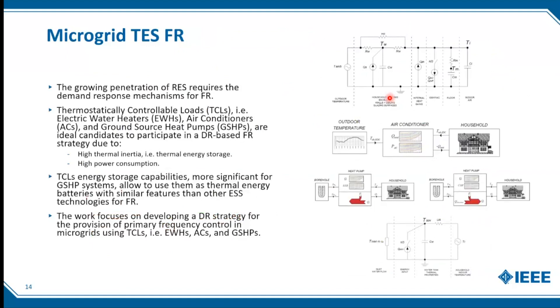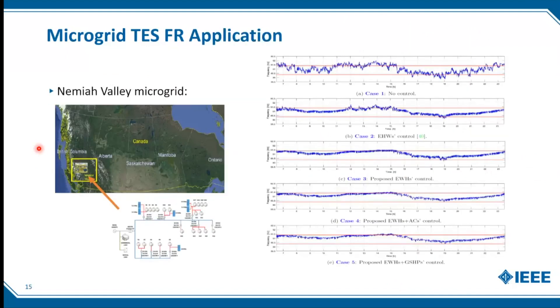We also looked at how to use storage systems at the house level — specifically air conditioning interacting with the house, ground source heat pumps in both heating and cooling modes, and thermal tanks to regulate frequency in a power system. We demonstrated with an application to a remote community in British Columbia that as you introduce these services, you can have a significant impact on frequency regulation. A system with a lot of solar components varied significantly such that the diesel generator could not regulate properly, but with ground source heat pumps you can regulate frequency within the required boundaries.